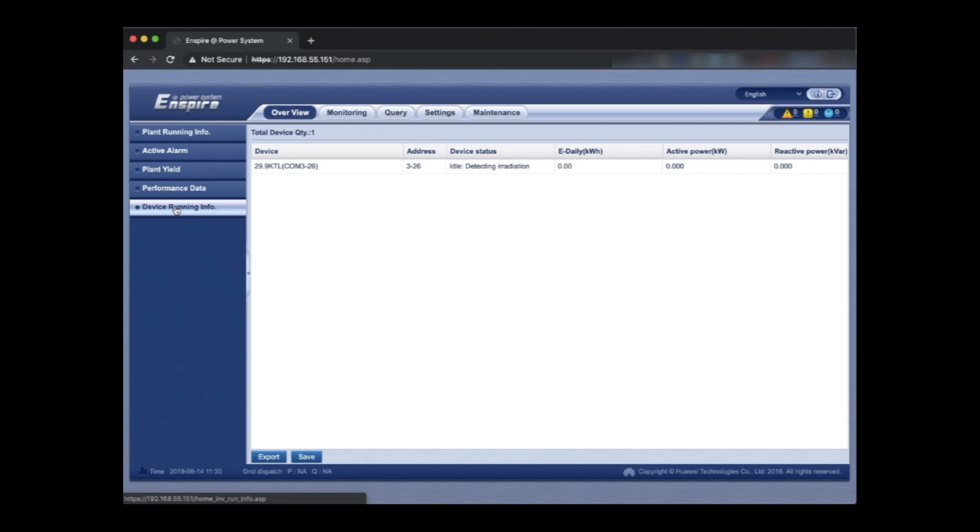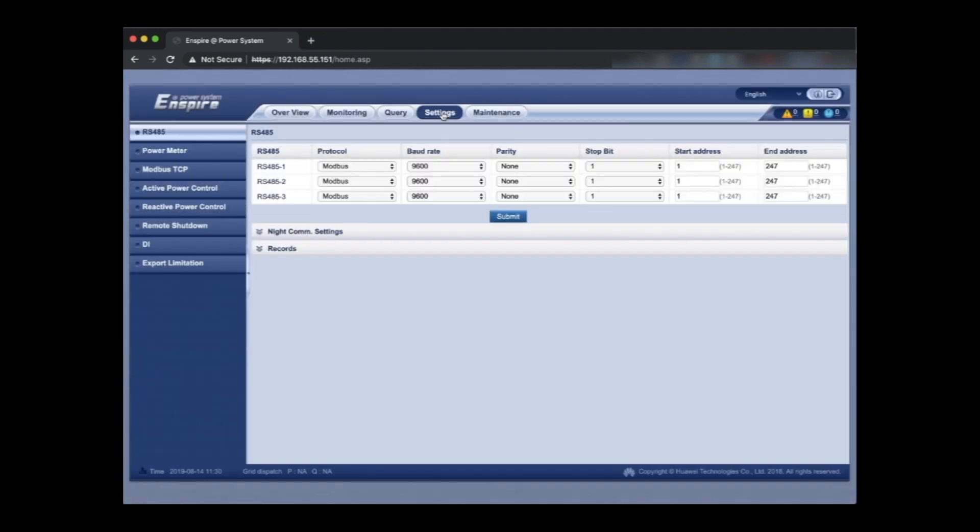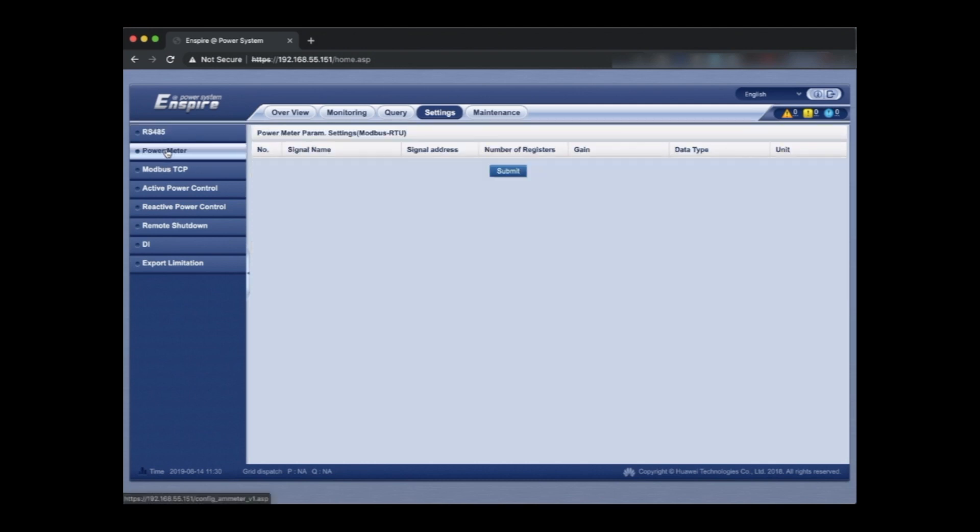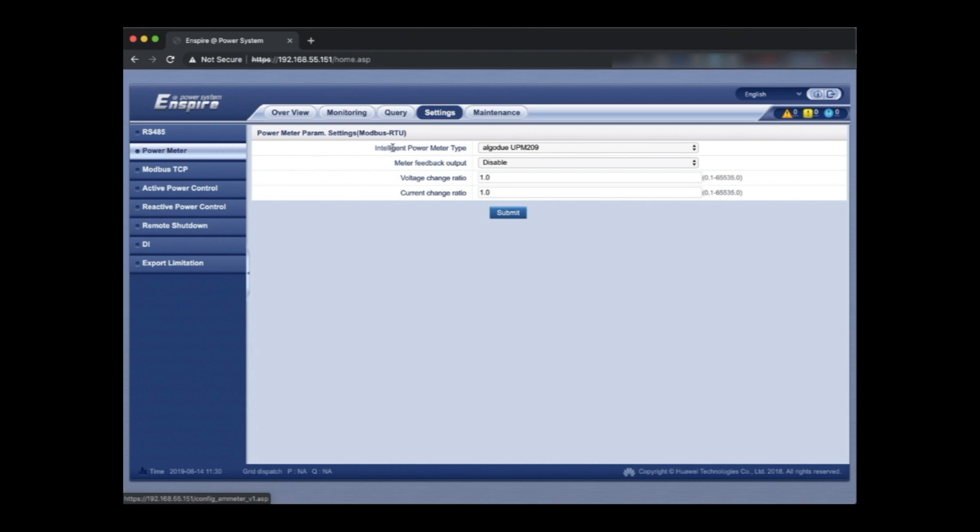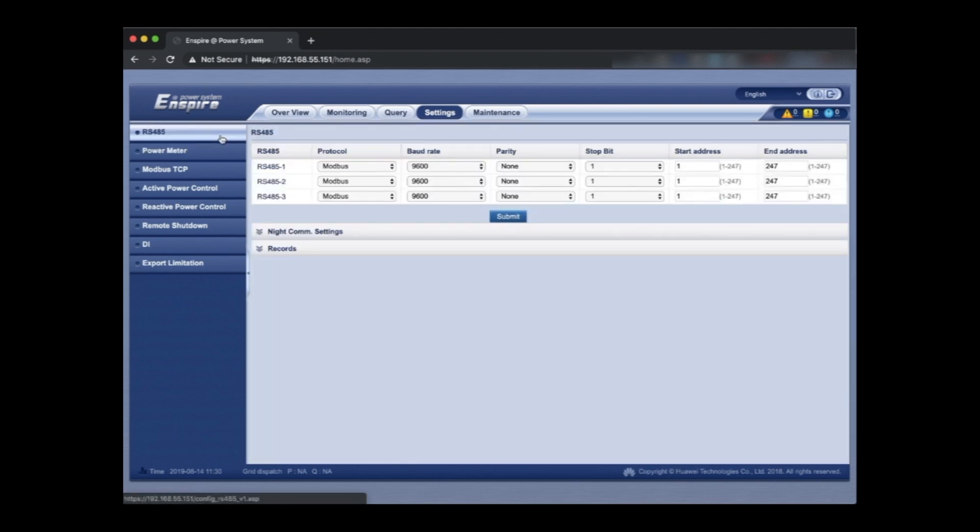Inverter's connected via RS-485. We're just going to add to this the smart meter. The smart meter will be under settings. You have to choose the right RS-485 port that you connect the smart meter to. In this case it was the second port. The baud rate is 9600. No parity. One stop bit. And we're using an algodue UPM209 and the meter can be added quite easily at this point.